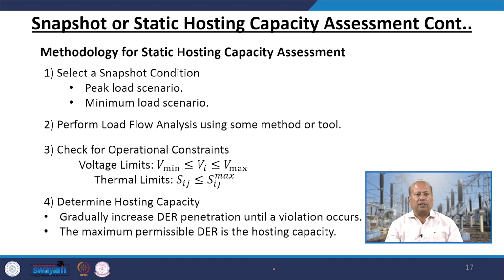Select a snapshot condition, peak load scenario as well as minimum load scenario. It performs load flow analysis using some method or tools. Check for operational constraints, that is the voltage must be below its maximum and more than its minimum, and the thermal limit must be less than or equal to its maximum capacity. Then we can determine the hosting capacity by gradually increasing the DER penetration until a violation occurs.